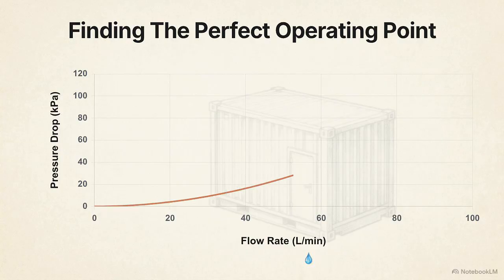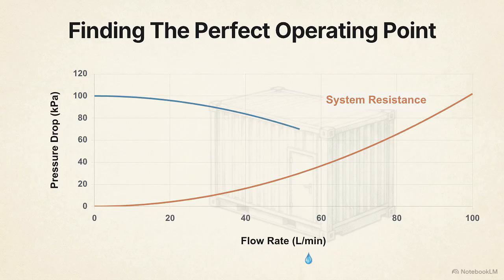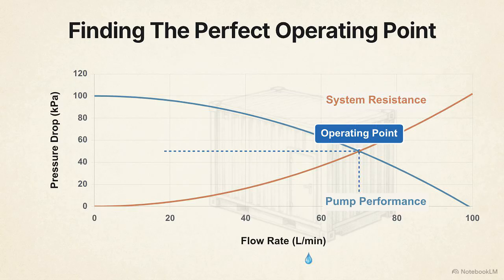This curve defines the pushback from the internal piping and cold plates. We match this against the downward-sloping pump performance curve, charting the pump's ability to maintain flow. The precise intersection of these two lines dictates the operating point of the system. This single node represents the exact flow and pressure the pump will deliver.